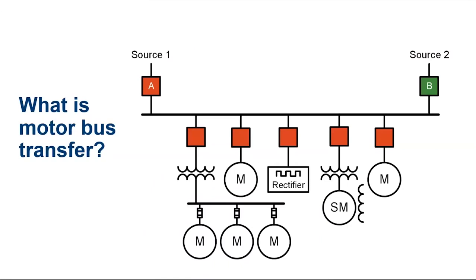Let's look at what motor bus transfer is. Motor bus transfer is the process of disconnecting a motor bus from its normal power source and safely reconnecting it to a designated alternate power source within a short period of time. All this has to happen within a short period of time, so we are allowing the critical processes to continue without damaging the equipment.